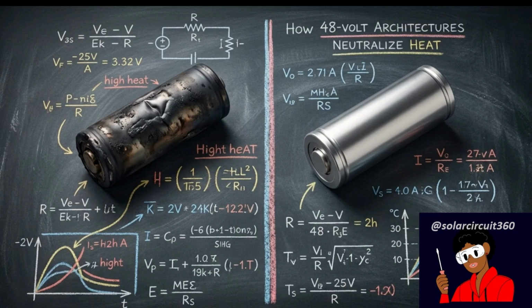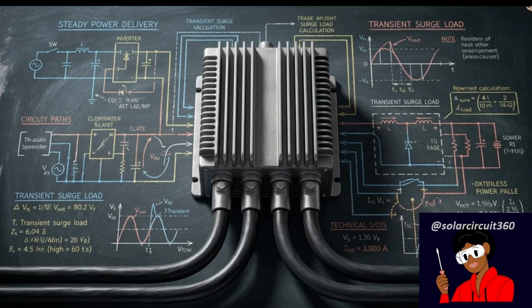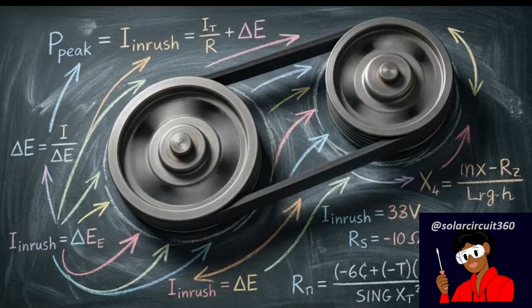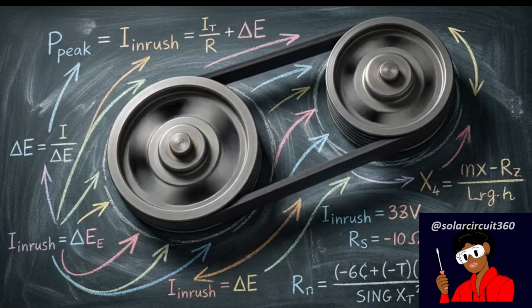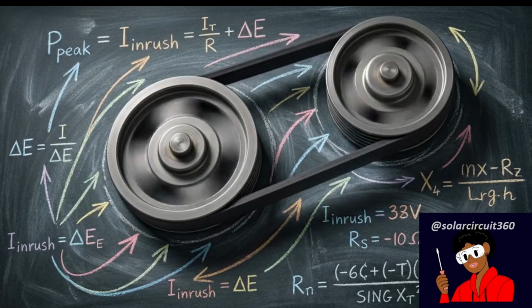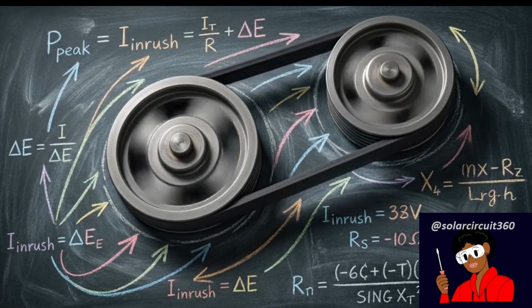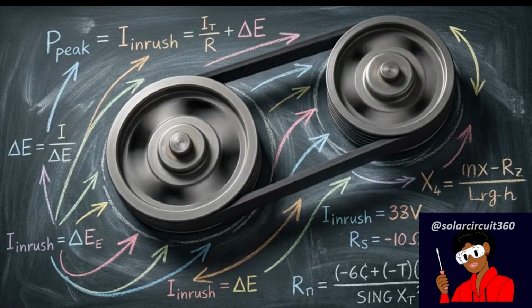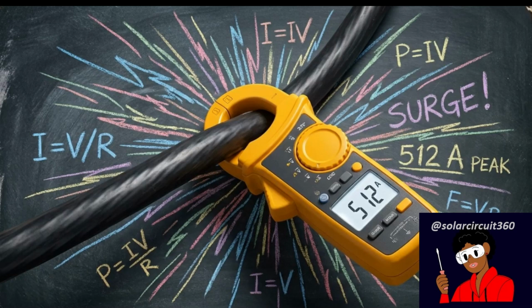Up to this point, we have only calculated continuous, steady power delivery. The physical strain becomes far worse during transient surge loads. Heavy inductive motors, like an off-grid air conditioner, require massive spikes of power solely to break the rotor's static inertia and start spinning. A sudden 3,000-watt surge on a 12-volt system forces the battery to dump over 500 amps of raw current in a fraction of a second.